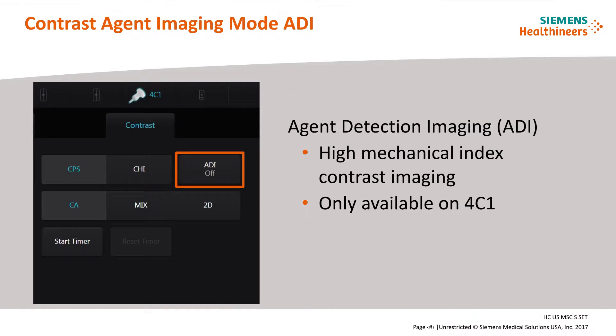There is an additional contrast imaging technique only available on the 4C1 transducer: Agent Detection Imaging, or ADI. ADI is a high mechanical index (MI) imaging technique that uses the emission properties of contrast agents to characterize their presence or absence in tissue. ADI has been used for pre-arterial and late phase radiology imaging applications and to detect early phase vascular structures or lesions; however, the contrast agent it was designed for is not currently available on the market.